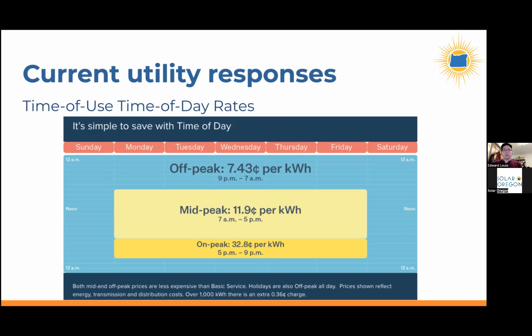Let's say in the wintertime there's not a lot of sun, so your battery isn't fully charged enough to cover the on-peak hours of energy usage. You can specify that you need, say, at least 50% of the battery full to make it through on-peak hours. But because it's winter and cloudy, you're not able to charge to 50% from solar alone. So you can program the battery to also buy and charge some electricity from the grid during off-peak hours, so it reaches 50% before the on-peak period starts.